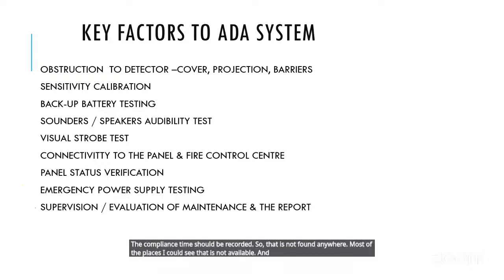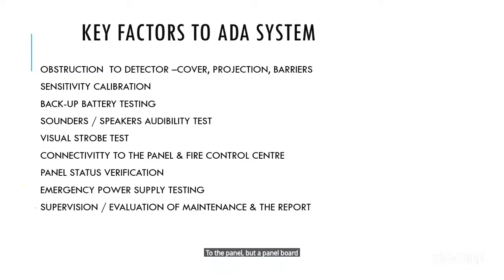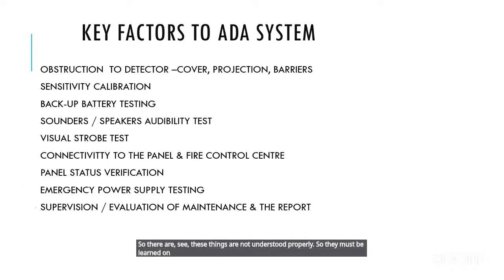And for panel status verification and emergency power supply testing, there is a testing method: how to test the emergency power supply to the panel board, and how to test the emergency power supply to the fire pump. These things are not understood properly. They must be learned and followed, so that the emergency power supply is connected automatically within 5 seconds when the normal power supply goes off. So like that, the systems are there, and that must be ensured.